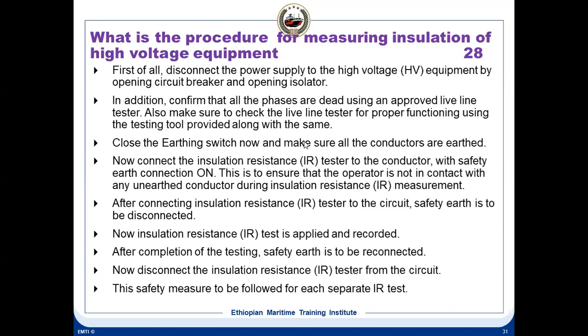Then close the earthing switch. There's an earthing switch on the breaker, close it. So you're grounding all the 3 phases coming from the generator to the switchboard. So generator to switchboard is being grounded. So any residual voltage on the line will be discharged. I will show you this in the practical time because we will rack out the breakers and do the Megger test, etc. I will show you at that time how the same procedure has to be followed, how you do this grounding and line tester, etc. I will show you in the lab.